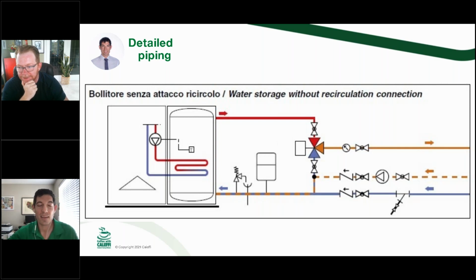So in the case you're using a thermostatic, you have to have the ability to throttle, like a globe valve, down. So you're sending some of that tank, some of the recirc water, back to the tank and not all of it right back into the inlet of the valve. It's a tricky commissioning step because you have to, in the middle of the night when there's no demand on the building, have somebody go in and throttle that globe valve down. So you're sending some of that back to the tank and not directly into the cold inlet. It's a very manual, very nuanced installation.